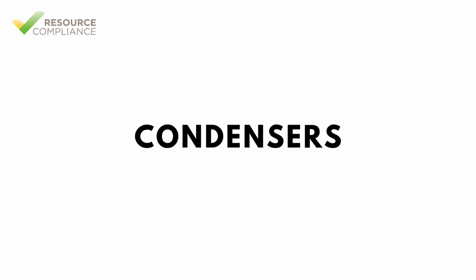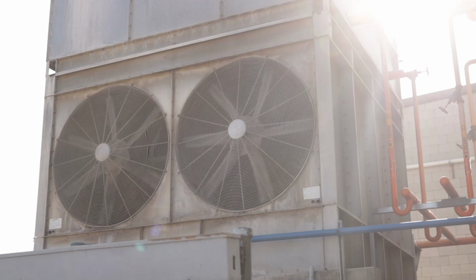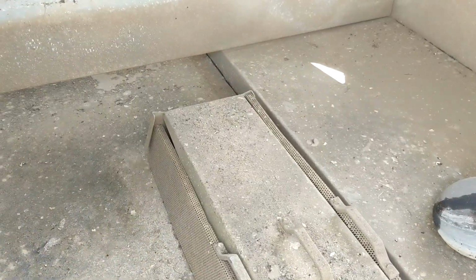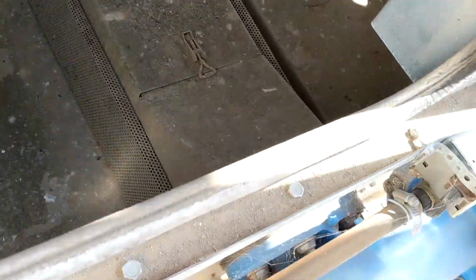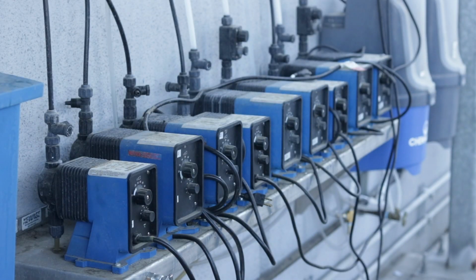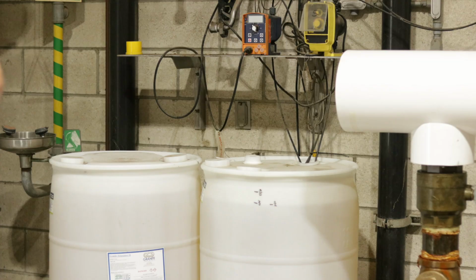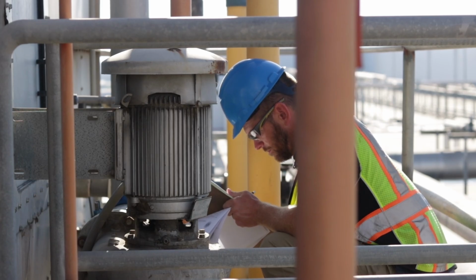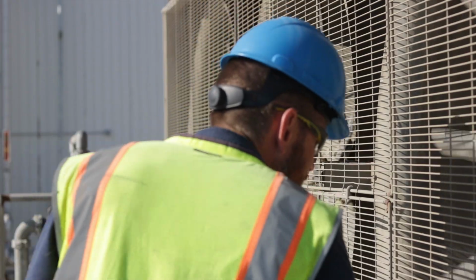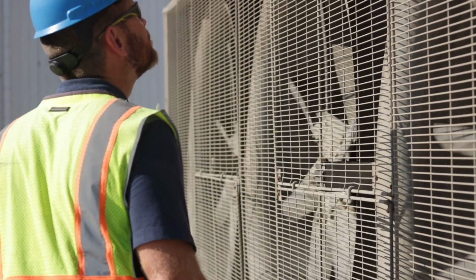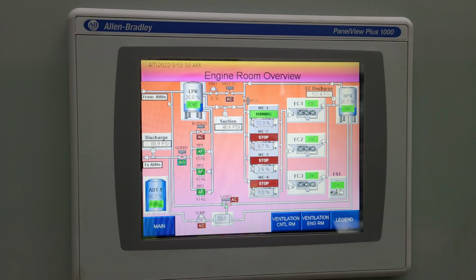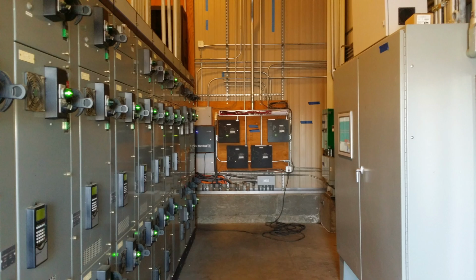To start an evaporative condenser, the operator must first make sure that the water level in the sump is adequate and the mechanical float is functioning. Condenser water chemistry must be maintained to prevent scale buildup and growth of algae or harmful bacteria. The operator should ensure that the chemical treatment system is functional. Next, the operator must turn on the condenser pump, followed by the fans. Depending on the configuration, this might happen at the PLC HMI or a switch and light panel.